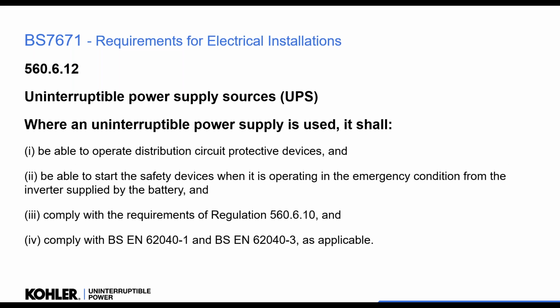Now in 7671, the only place you'll find uninterruptible power supply written is under the safety systems in chapter 560, and it talks about where an uninterruptible power supply is used, it shall be able to operate the distribution circuit protective devices and start them when it's in an emergency condition running from inverter on battery.